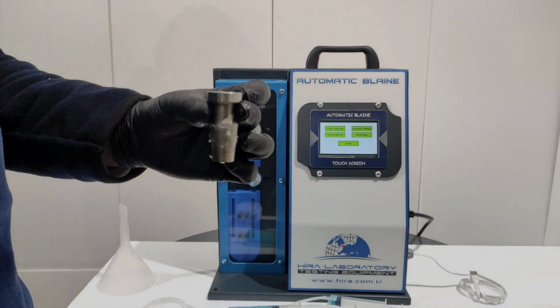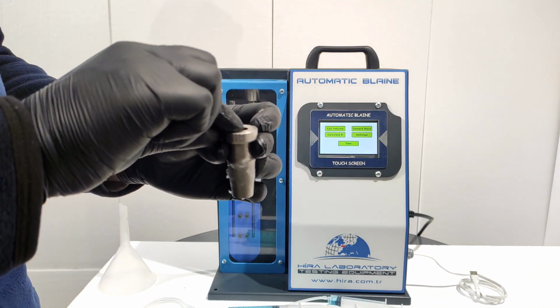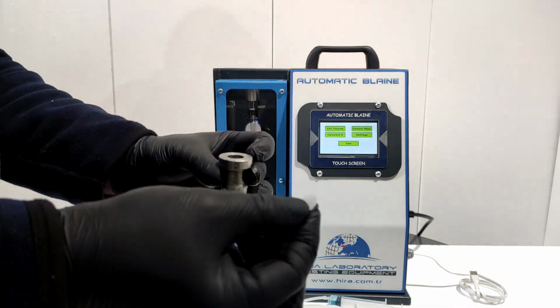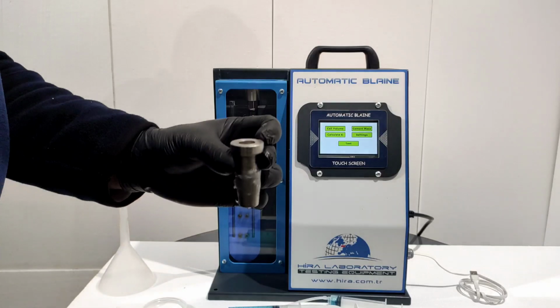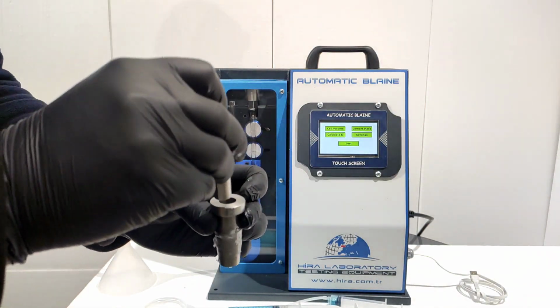The device should now be calibrated. Gently shake the reference cement by tapping it with your fingers for 2 minutes. Lubricate the cell surface with grease to prevent airflow from the cell surface. Put a perforated disc in the cell and tamp it with the rammer. Put a filter in the cell and tamp it with the rammer.